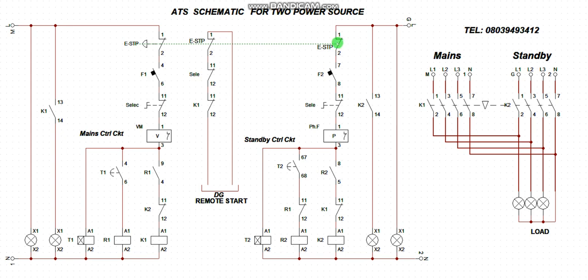Now, when this one is enabled, power comes from this supply, from this other end, my standby. It comes to the push button, from the push button to the single pole MCB, from the MCB to my selector switch. This selector switch enables you to cut off the logic, cut off the supply while carrying out your maintenance. That is the essence of this.